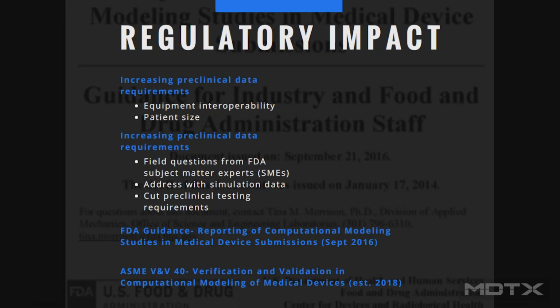Down at the bottom, the FDA guidance on reporting computational modeling studies came out in 2016. The draft came out in 2014. It's out. It provides a framework. The ASME V&V 40 is a V&V guidance document and standard for computational modeling in medical devices. Last I heard, it was supposed to come out last November. I haven't seen an updated date for it, but it's not out quite yet either, so it should be out sometime this year, would be my guess.